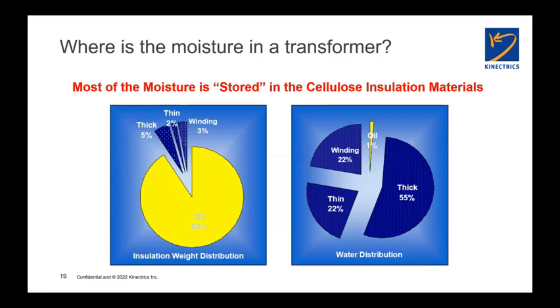Well, this is interesting because on the left side, you see a pie chart that shows the weight distribution of the insulation in a transformer. And in a paper oil insulated transformer, in rough numbers, about 90% of the weight is the fluid, it's the oil. And only 10% of the insulation system is actually comprised of the cellulose materials, whether they're winding conductor wrap, or what we call thin, which would be like your caps and collars, and thick, which would be like your core clamping plates, etc. But as far as the water distribution goes, by far, most of the water is in the paper, in the cellulose, not in the oil.